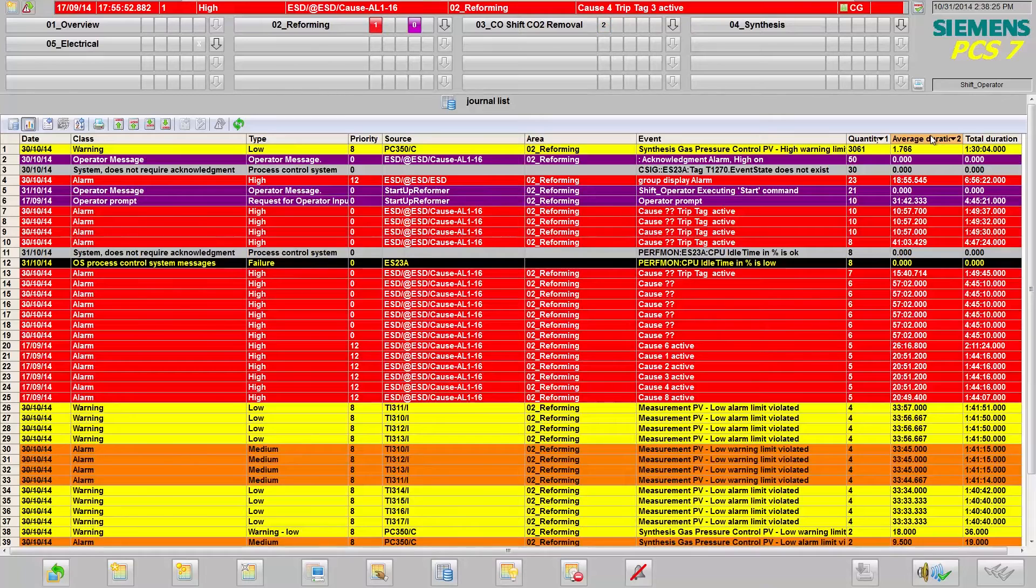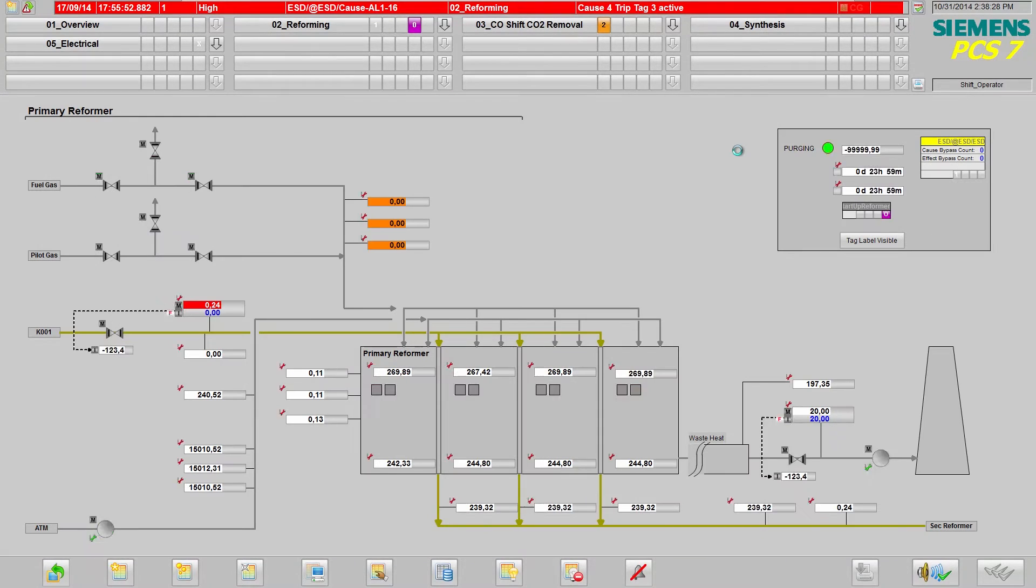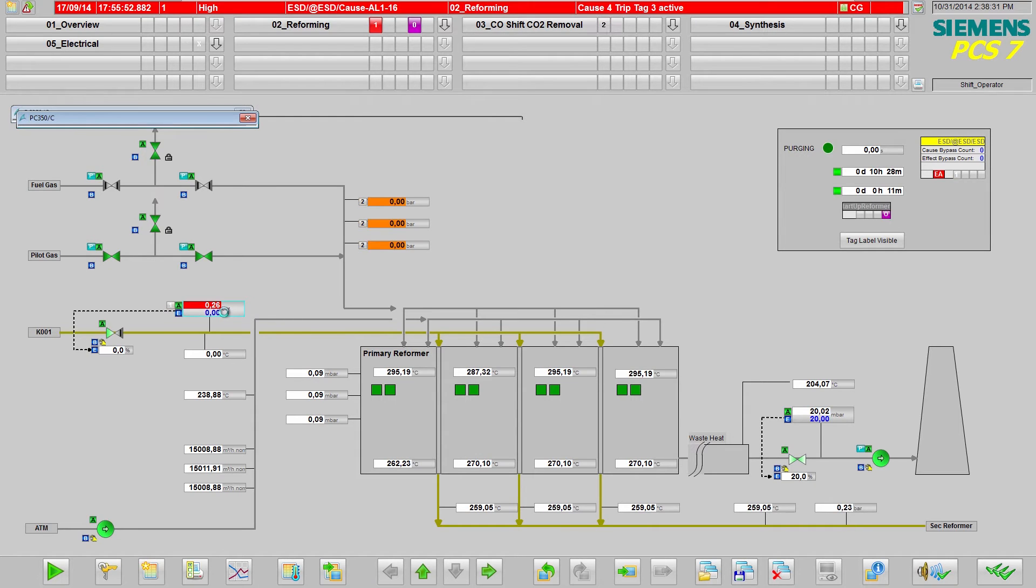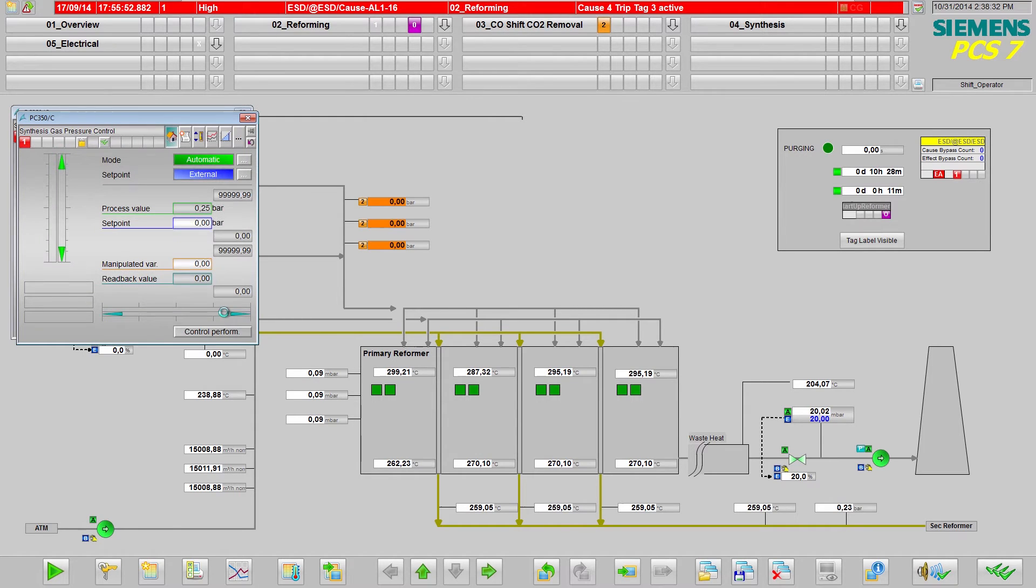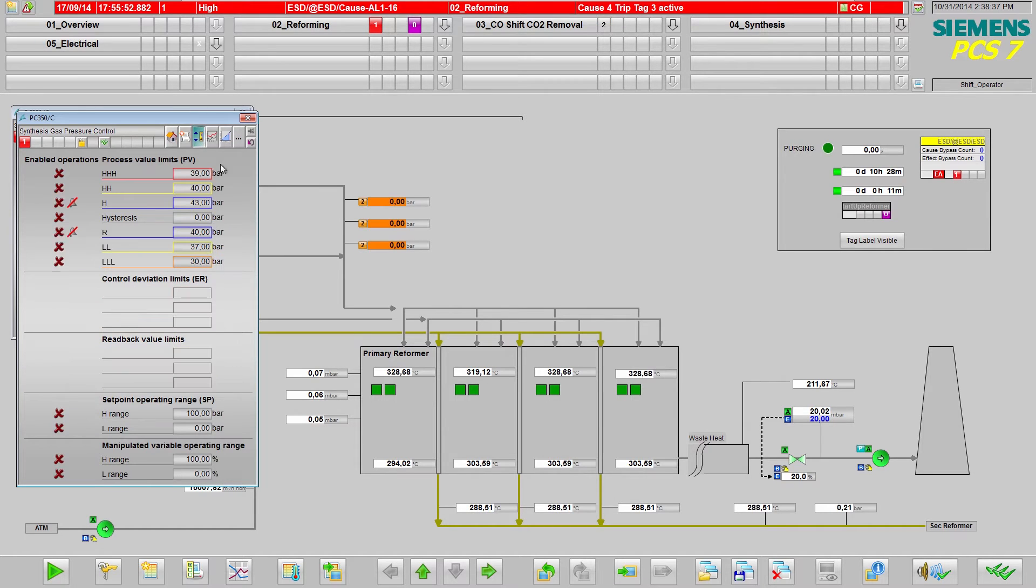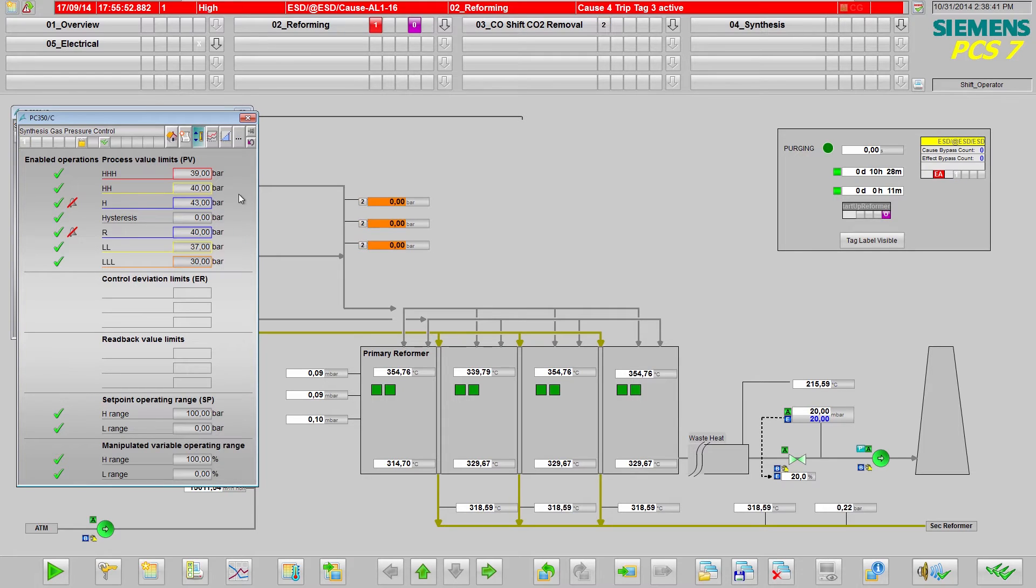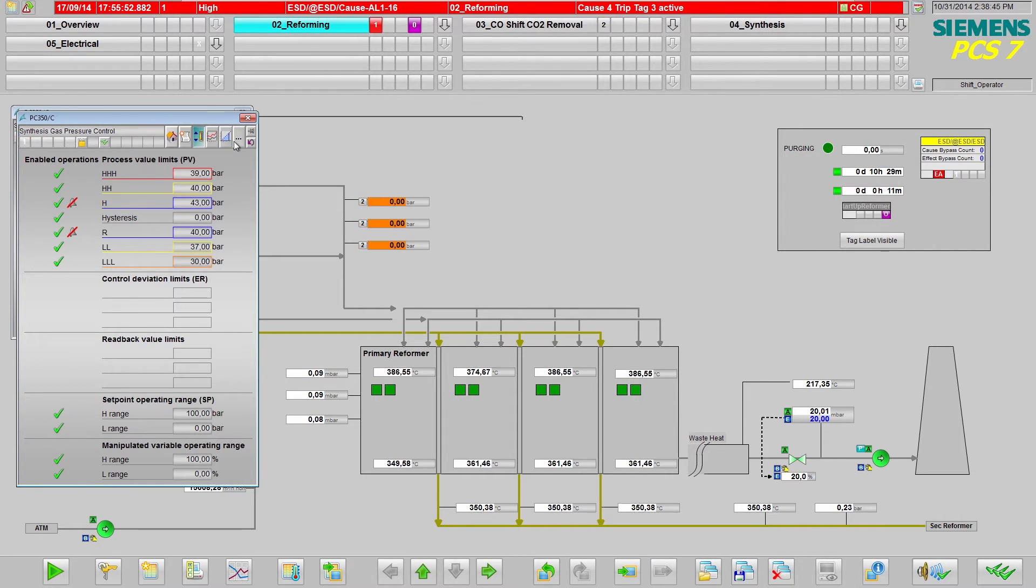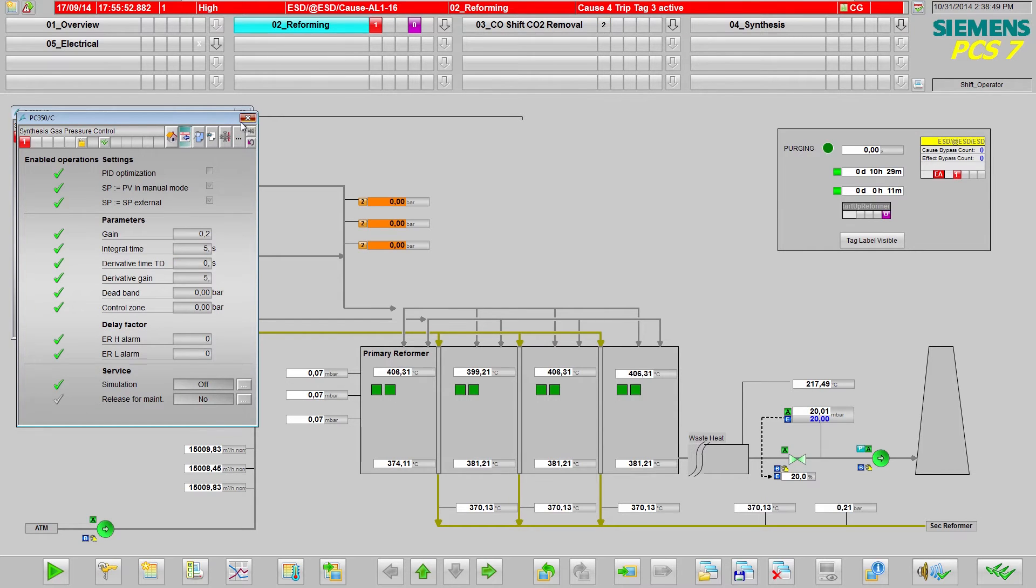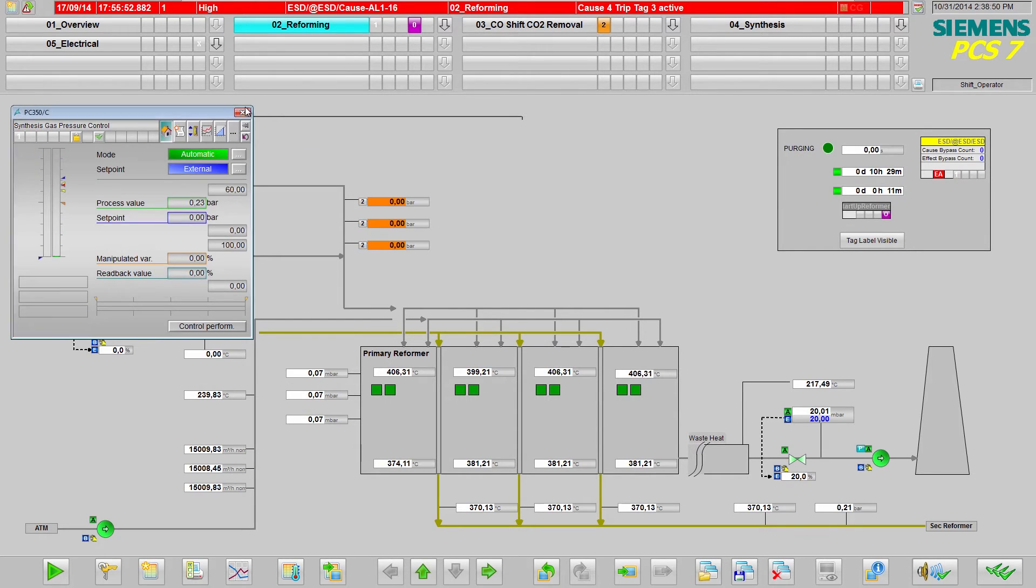In this way, I can check whether an alarm is a sporadic alarm that is triggered too easily, meaning that the limits must be readjusted, should be suppressed in a certain operating state using smart alarm hiding, or is generally irrelevant and can be deactivated. Adjusting the alarm limits or changing the control parameters are further optimization options.